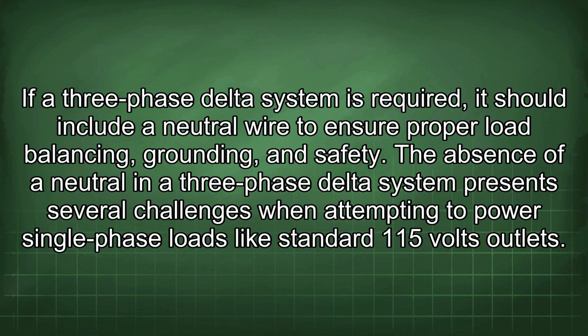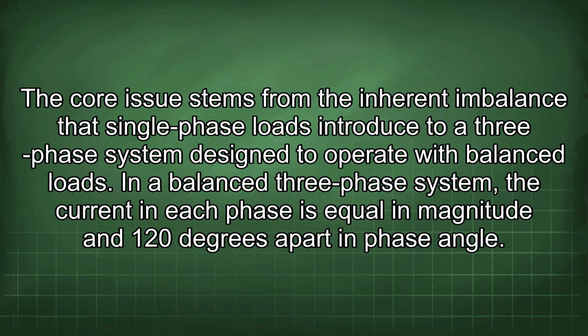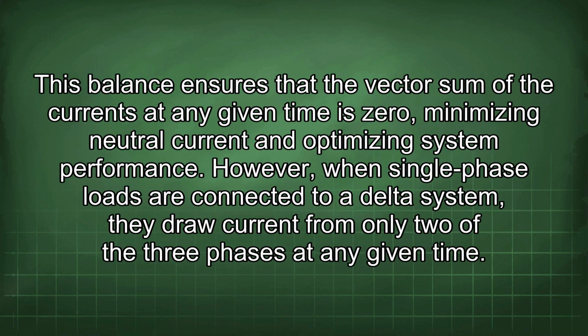The absence of a neutral in a three-phase delta system presents several challenges when attempting to power single-phase loads like standard 115 volts outlets. The core issue stems from the inherent imbalance that single-phase loads introduce to a three-phase system designed to operate with balanced loads. In a balanced three-phase system, the current in each phase is equal in magnitude and 120 degrees apart in phase angle. This balance ensures that the vector sum of the currents at any given time is zero, minimizing neutral current and optimizing system performance.